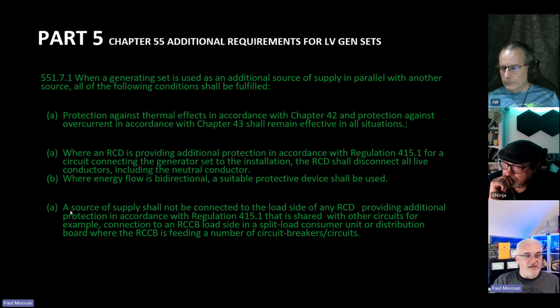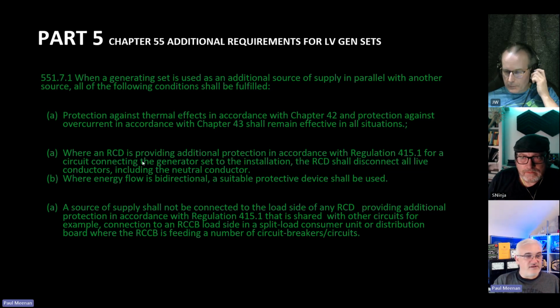The last one is, and all our lettering has gone weird for some reason, part (iv). A source of supply shall not be connected to the load side of any RCD providing additional protection in accordance with 415 that is shared with other circuits. For example, connection to an RCCB load side in a split load consumer unit, or distribution board where the RCCB is feeding a number of circuit breakers.